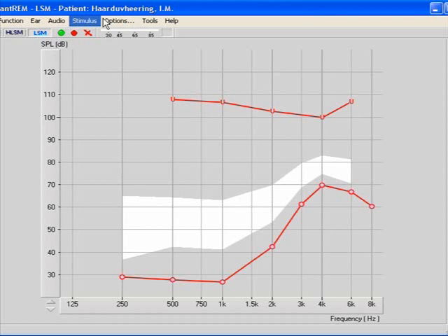Modern hearing instruments provide patients with unprecedented abilities to understand speech in background noise. Much of this improvement is due to the development of adaptive directionality systems in hearing instruments. These systems analyze the acoustic environment and then adjust the sensitivity of the directional microphones so that they are most sensitive to speech, usually in front of the patient, and less sensitive to other sounds.